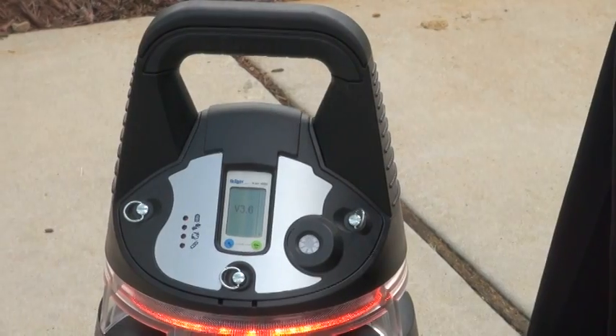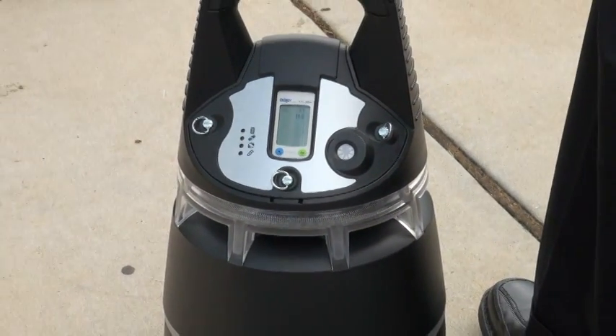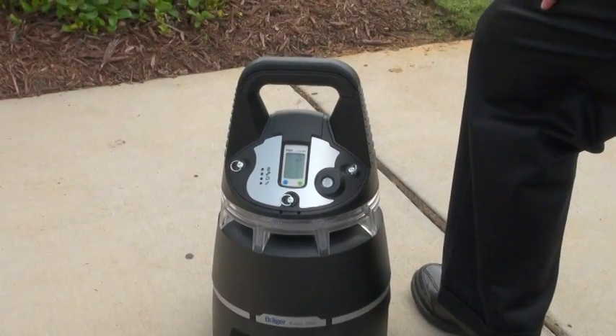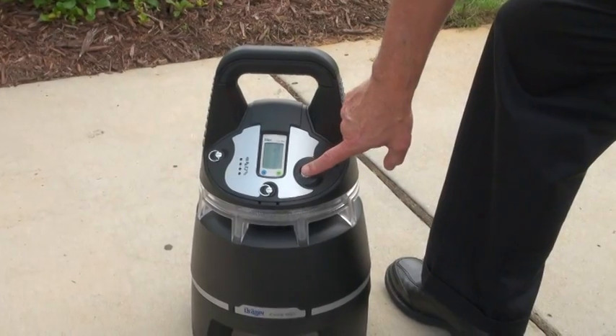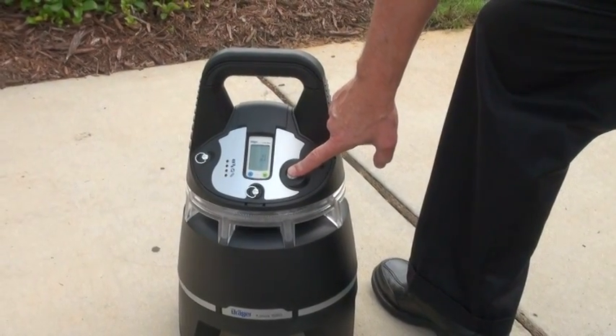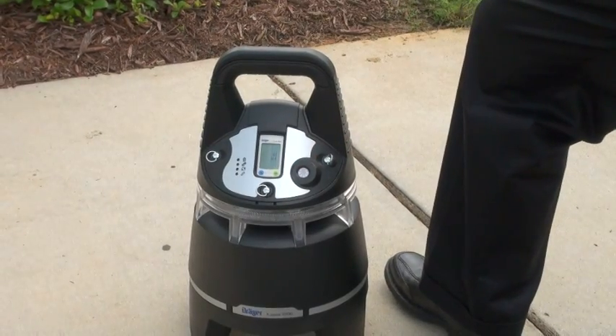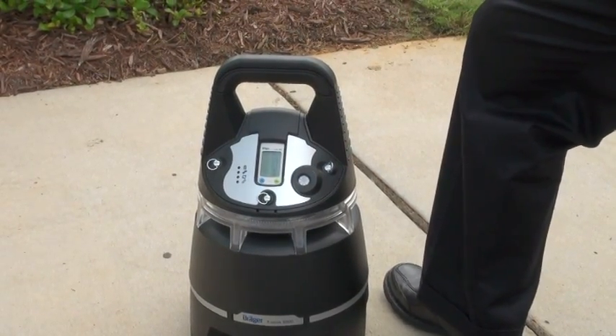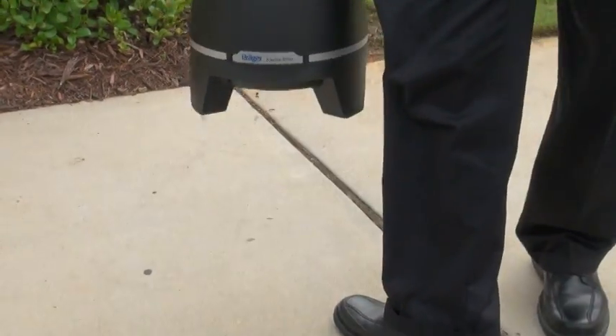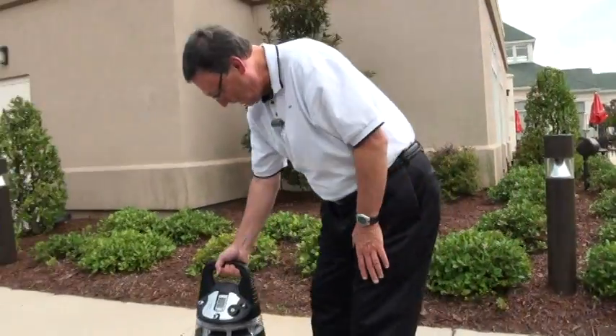It's now on. You can see the lights flashing on the X-Zone and hear it beeping. It has an installed pump and wants a leak test performed. Cover the pump inlet until you get a steady tone, then release. Now it's up and running. Pick up the X-Zone and take it to wherever you want to place it and set it down.